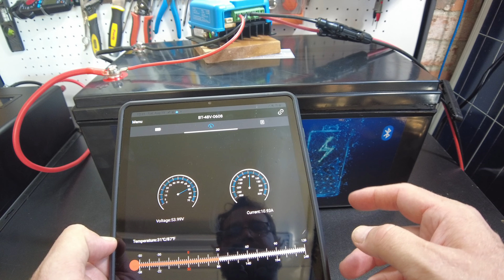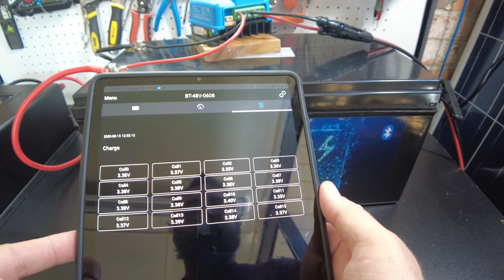You can scroll over to this next page. Shows our current, so we're pushing in about 11 amps, temperature, the voltage, and then individual cell voltages. All the individual cell voltages look good, they're all very close - 3.38, 3.37, 3.39 kind of area. I don't see... well, we got one that's 3.4, so that's a little bit higher than the rest of them. I'm going to let this continue to charge up, and when it's fully charged we'll finally get to our discharge test.